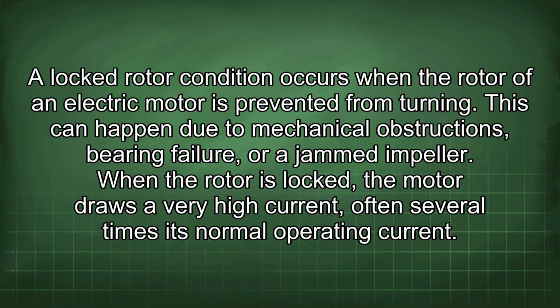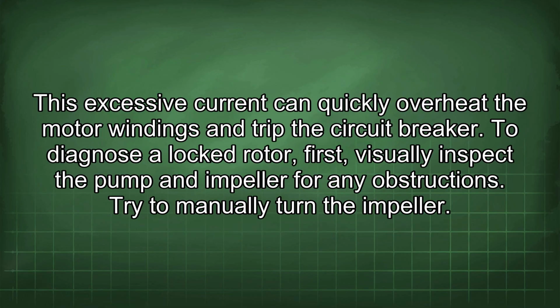A locked rotor condition occurs when the rotor of an electric motor is prevented from turning. This can happen due to mechanical obstructions, bearing failure, or a jammed impeller. When the rotor is locked, the motor draws a very high current, often several times its normal operating current. This excessive current can quickly overheat the motor windings and trip the circuit breaker.